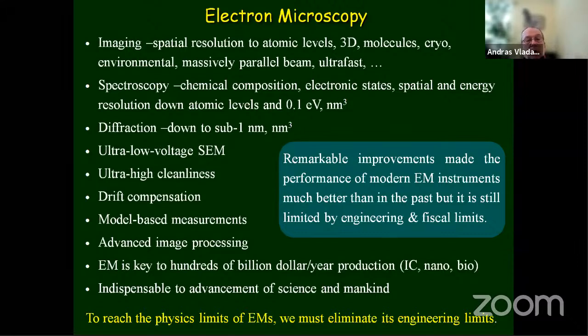So drift compensation is one of the critical parts, because we essentially want to keep the sample motionless at a few 10 picometer levels, which is absolutely not trivial, especially in the case of an SEM, but even for TEM it is a challenge. Model-based measurements, which essentially entail use of physics in the interpretation of the measured data, and advanced image processing, all kinds of advancement in image processing can be and need to be applied to electron microscopy.